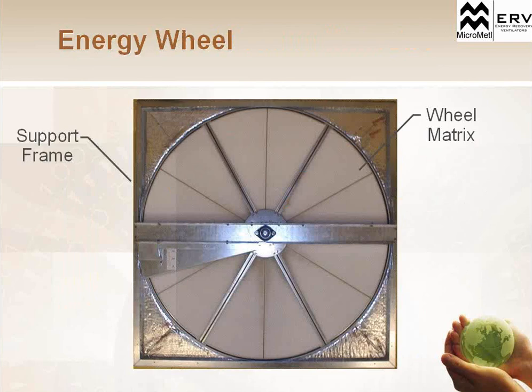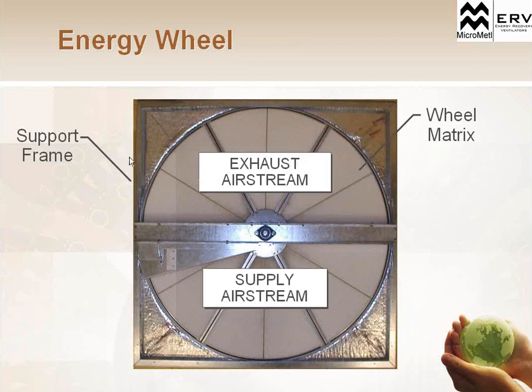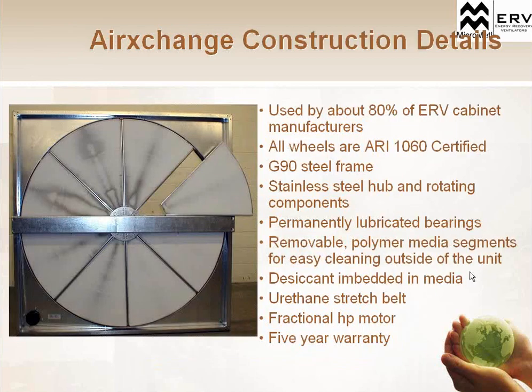If we look at the energy wheel itself, we'll break down the wheel so you can see it. This is a basic wheel that you would see in a commercial application. We've got the frame of the wheel itself. We've got the division between the two airstreams, that sealed division here. We've got each of the wheel matrix pieces, kind of like pieces of a pie. Because these wheels can handle large CFMs, they can get pretty large in size, so we break down the wheel itself into little pie pieces that are able to be taken out and put together. This is the exhaust airstream up here, and this would be the supply airstream down here. So this support would separate the two airstreams. The wheel would spin in between them. As you can see, there's one of the pie pieces that comes right out. They pop out of the system.